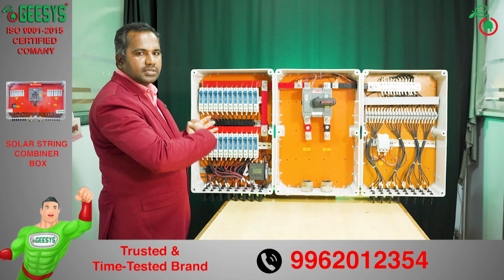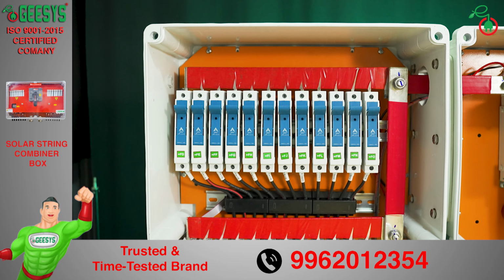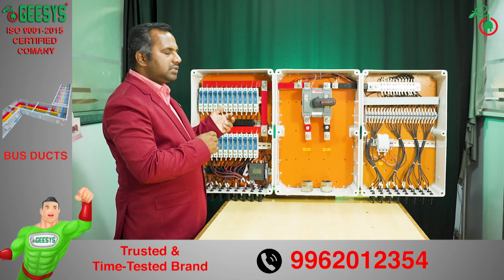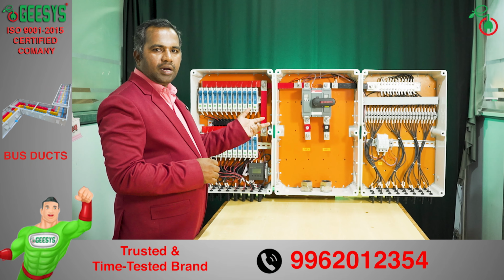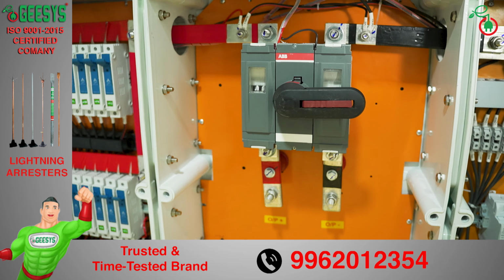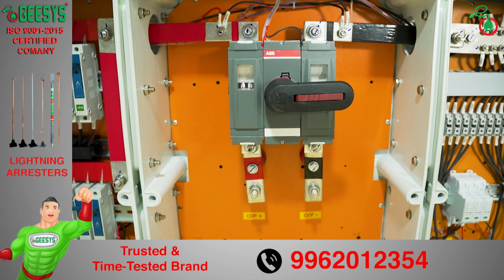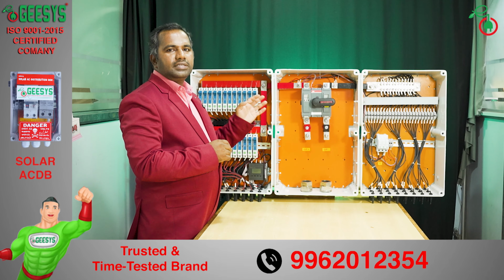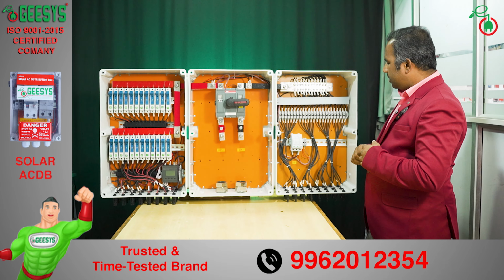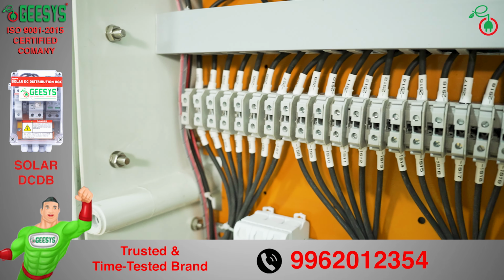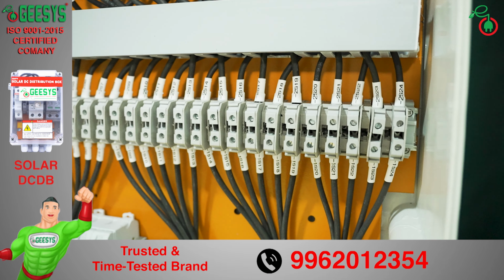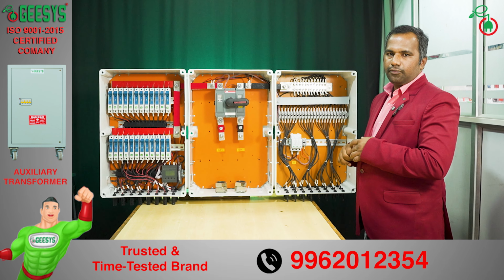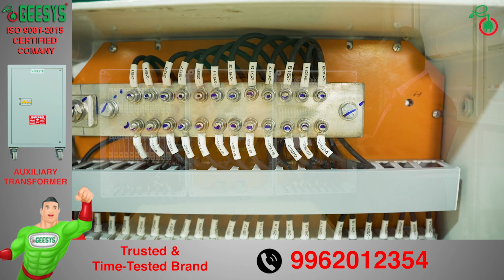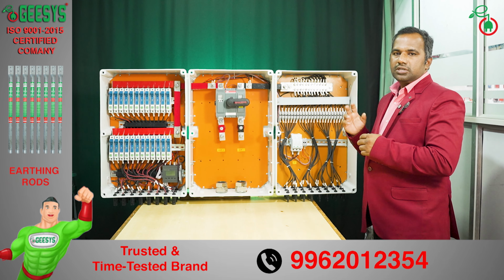So the entire string combiner box we have used ETP grade copper busbar which is tinned. Output of this string combiner box we have used a DC isolator. This is 1500 volt DC rated 500 amps DC isolator. Negative side of the string combiner box we have connected through terminal block. This is again 1500 volt DC rated terminal block. We have used SS304 A70 grade SS bolt nuts here, and we have provided a surge protection device.